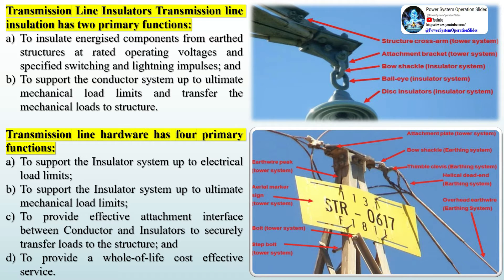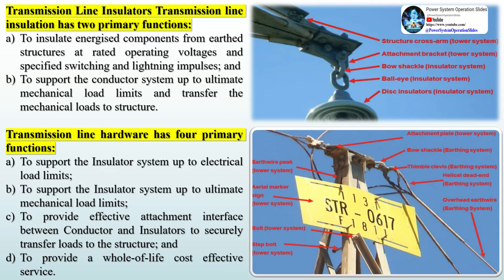Transmission line insulation has two primary functions: to insulate energized components from earthed structures at rated operating voltages and specified switching and lightning impulses, and to support the conductor system up to ultimate mechanical load limits and transfer the mechanical loads to structure. Transmission line hardware has four primary functions: to support the insulator system up to electrical and ultimate mechanical load limits, to provide effective attachment interface between conductor and insulators to securely transfer loads to the structure, and to provide life-cost-effective services.